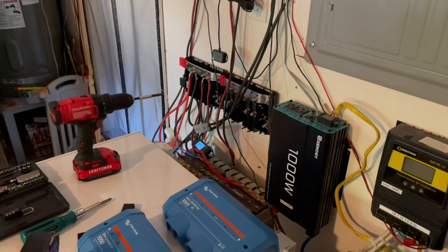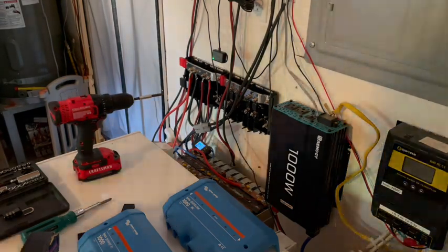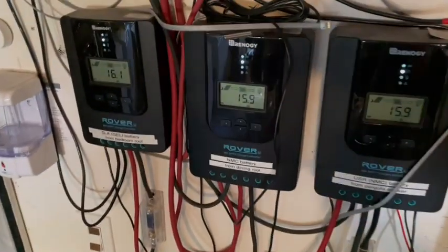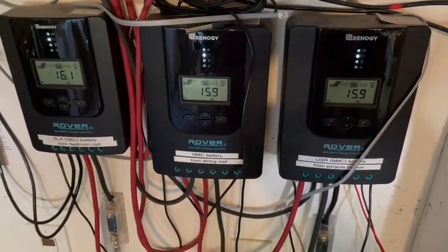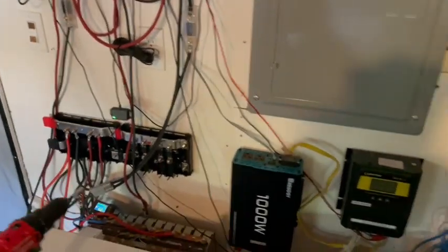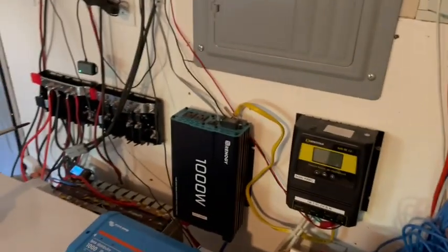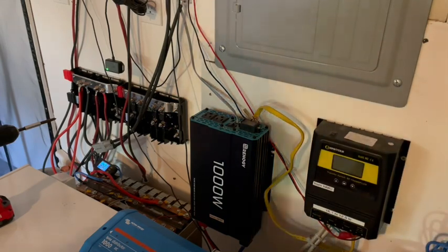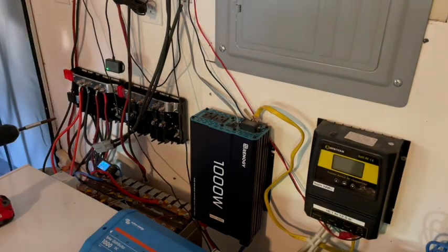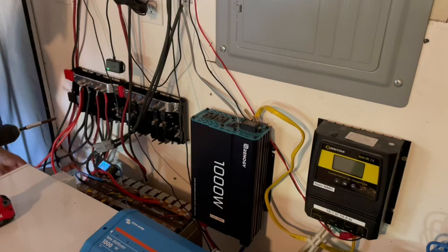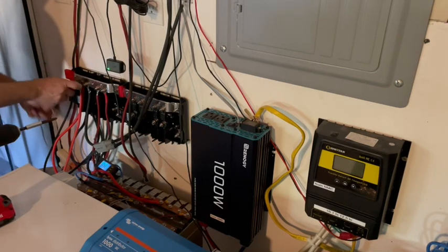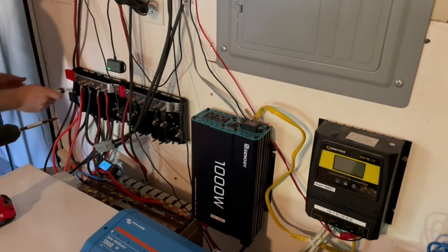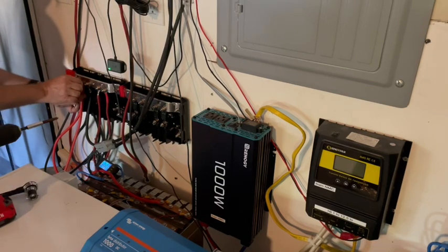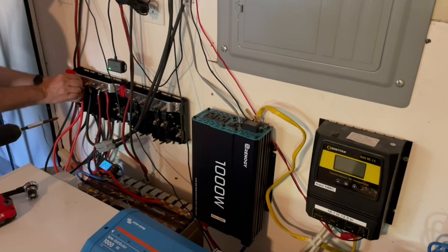I have 3 disconnects, because I have 3 arrays. Okay, so now all of my MPPTs are indicating the solar is disconnected, because I have now de-energized the charging lines, but the battery is still connected and the discharging line is also disconnected. So the battery is now the only thing connected to this bus bar. Everything else is just a wire going to some components that are off.